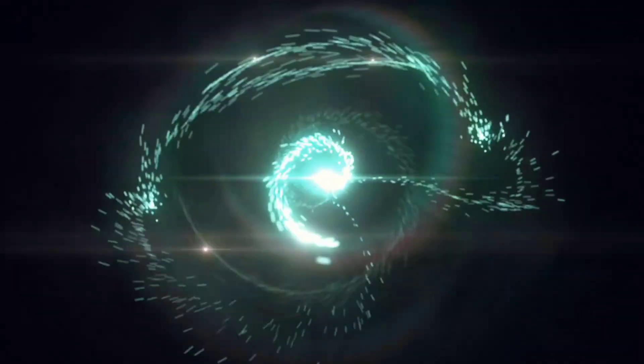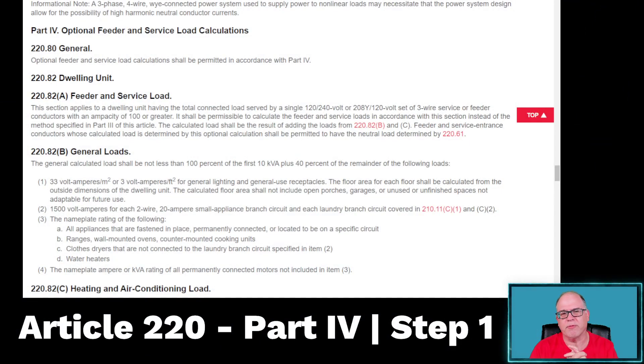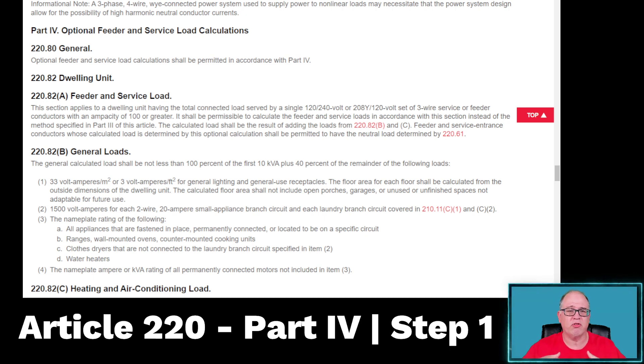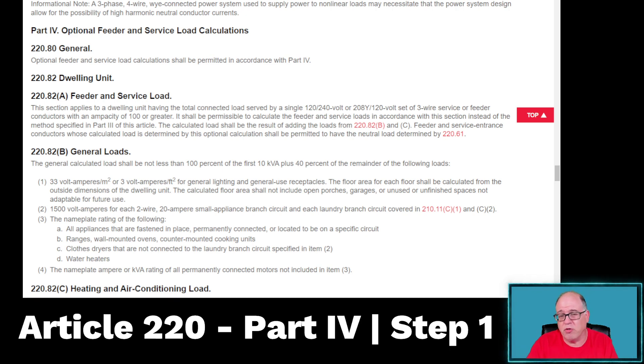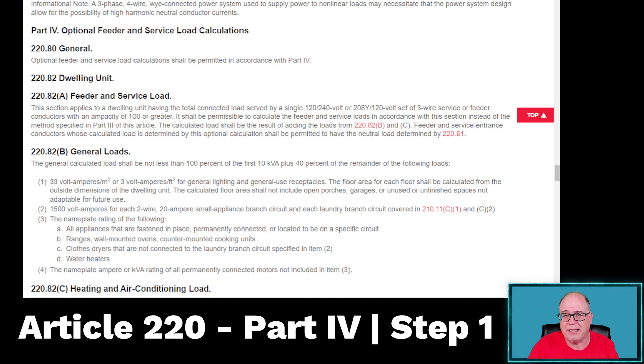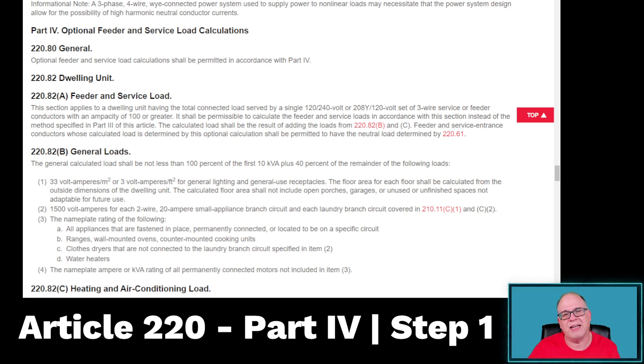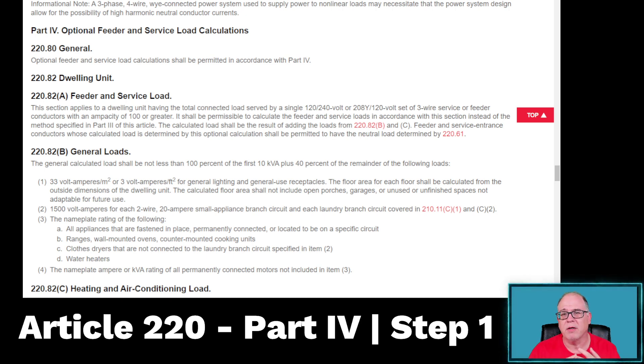Let's look at the code real quick. This is where we're at in the National Electrical Code — Part 4, broken down into A, B, and C. Part A gives you general information and tells you what this is applicable to. You can use this optional method if your service is 100 amps or greater. So if you're doing a feeder to an individual dwelling unit in a multifamily building and the load calculation comes out to less than 100 amps, then you can't use the optional method — you'd have to use the standard method. It has to be at least a 120/240 volt system or a 208Y/120 volt system, which is a three-wire service or feeder.